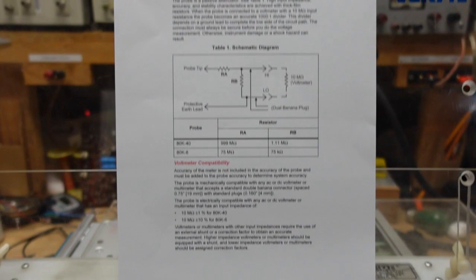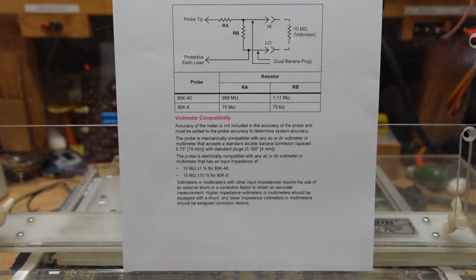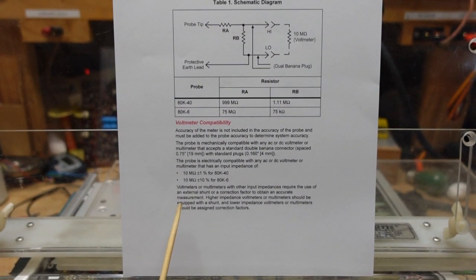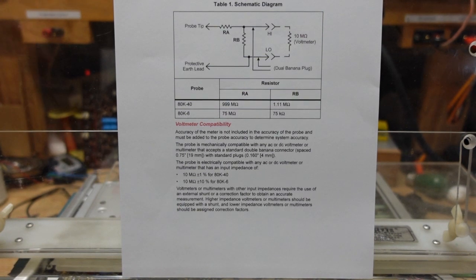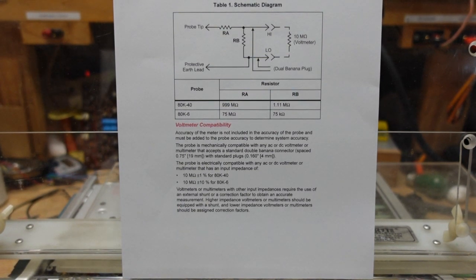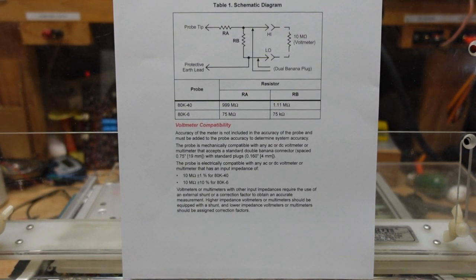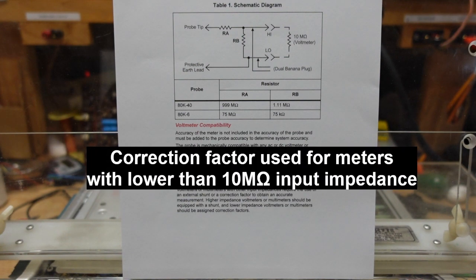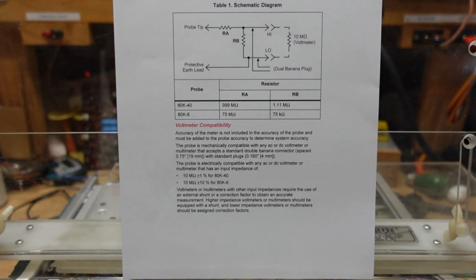If you have a meter that has other impedances, it tells you here at the bottom you use either an external shunt if it's higher than 10 megohm or you need to use a correction factor. Fortunately, as I've said several times, most digital multimeters have an input impedance of 10 megohm.